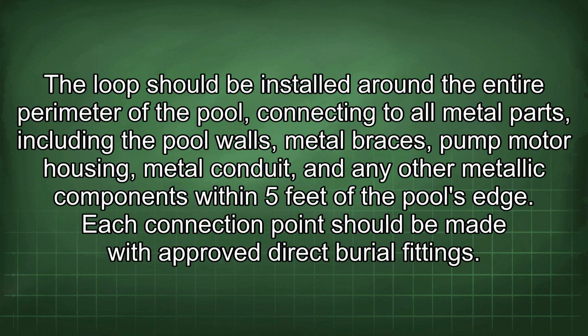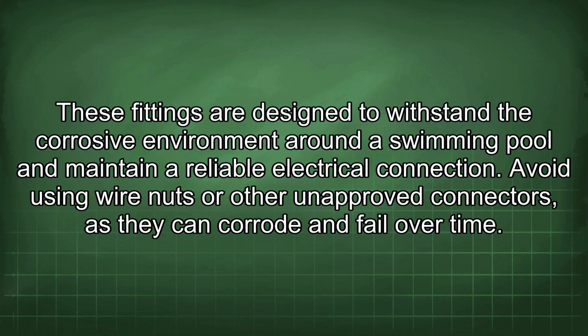The loop should be installed around the entire perimeter of the pool, connecting to all metal parts, including the pool walls, metal braces, pump motor housing, metal conduit, and any other metallic components within 5 feet of the pool's edge. Each connection point should be made with approved direct burial fittings. These fittings are designed to withstand the corrosive environment around a swimming pool and maintain a reliable electrical connection. Avoid using wire nuts or other unapproved connectors, as they can corrode and fail over time.